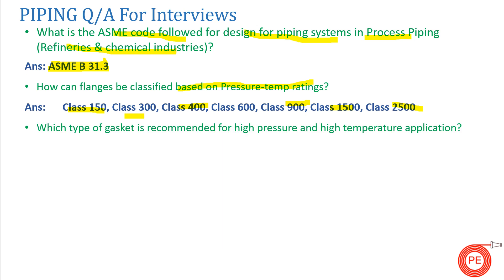Which type of gasket is recommended for high pressure and high temperature applications? This is an important question if you are going for a power plant or steam application interview. The gasket material used is a spiral wound metallic gasket. In this gasket, there is a metallic insertion inside that is spirally wound.